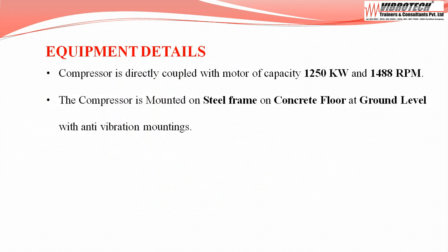The compressor we are going to see is coupled directly with a motor of capacity 1250 kW and running at 1488 RPM. The compressor is mounted on a steel frame, on a concrete floor at ground level, with anti-vibration mounting.